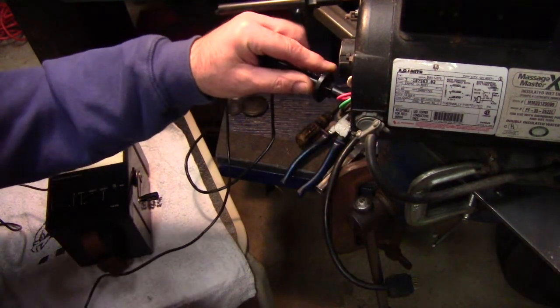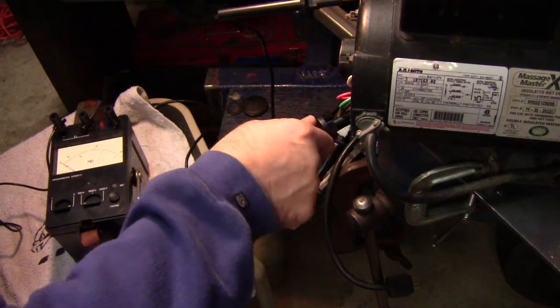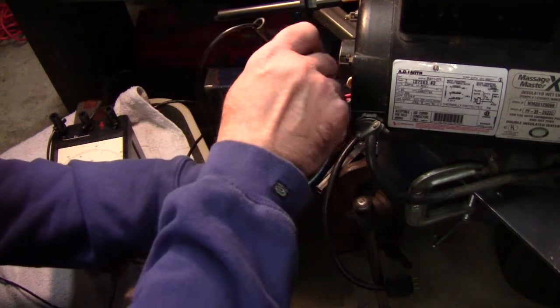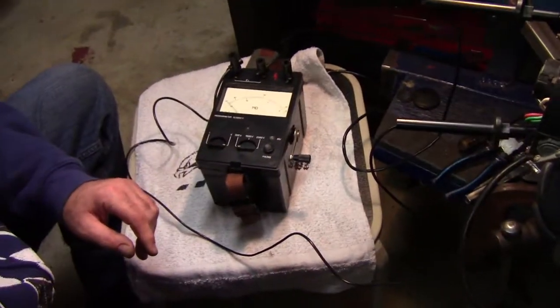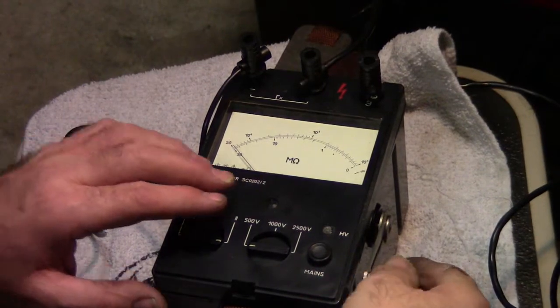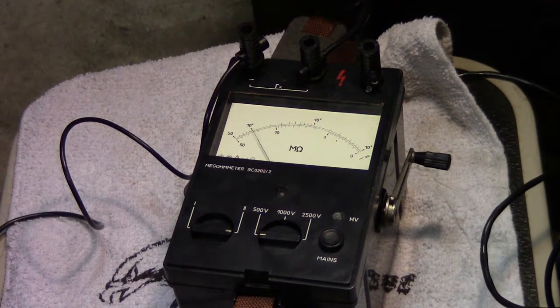Now let's go check the low speed side of the motor — it's a different winding, so it may give us a different reading. Let's go back to the megohmmeter and try the low speed side out. And again, no short there. It's going up over 1,000 mega ohms at 500 volts. So we're doing good.